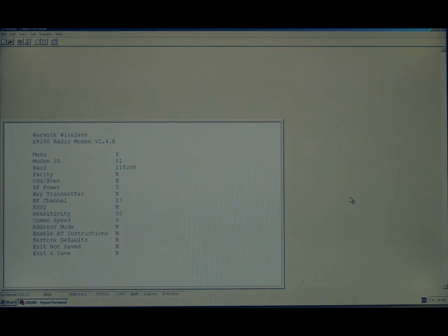The transmitter can be keyed. This is a very powerful feature which allows you to do a very quick and simple radio site survey. You can key the transmitter on the base station and then use a second X9200, which will be powered by a battery. And as long as the RX LED is on the receiving modem, then you're in radio range.